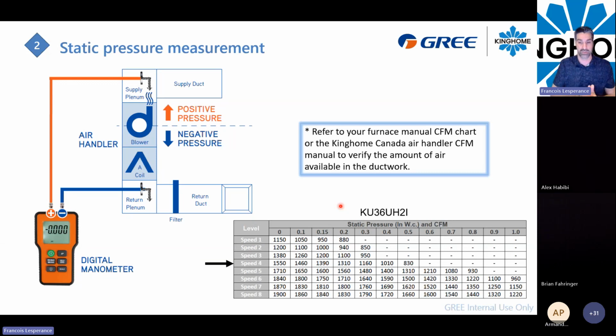By default, using an air conditioner, we always recommend using high speed. But if you take the measurement and make sure you have the right amount of CFM, maybe medium speed can be the perfect fit for that home. This is why you need to take those measurements, to assure you have the right amount of CFM. So you need to pull out the manual of your furnace or your air handler, take this chart right here, and just by taking your measurement, make sure you have the right amount of CFM.